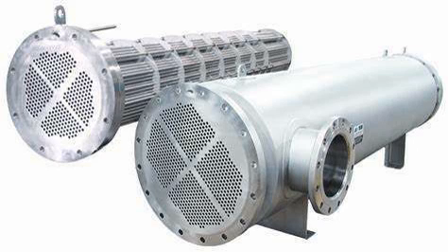When used in open loops, these heat exchangers are normally of the gasket type to allow periodic disassembly, cleaning, and inspection. There are many types of permanently bonded plate heat exchangers, such as dip-brazed, vacuum-brazed, and welded plate varieties, and they are often specified for closed-loop applications such as refrigeration.